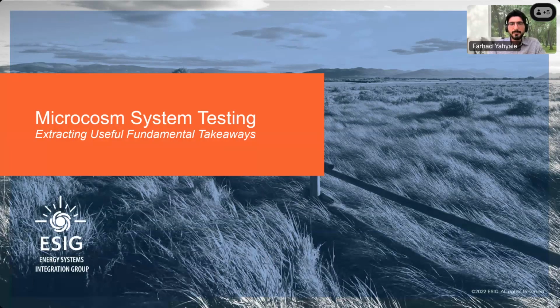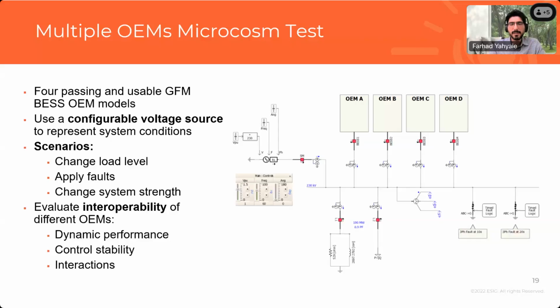The next set of tests was on the Microcosm system, which interconnected the four GFM models that passed the NERC white paper requirements into a smaller test system connected to a programmable voltage source. This let us change the frequency, voltage, and phase angle of the source and apply disturbances such as load changes and faults, to investigate interoperability among these different GFMs, their dynamic performance, and whether any control instability or adverse interactions occur when combining different OEMs. We ran a few test scenarios.